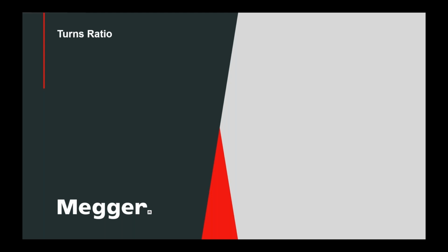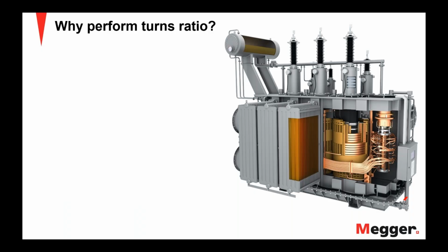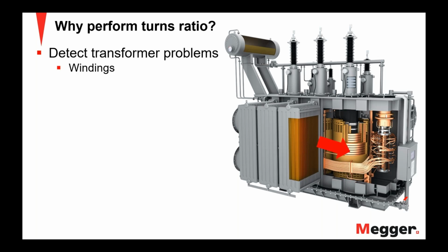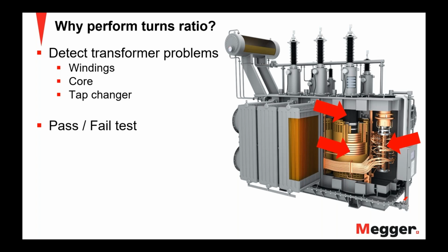But now if we look at the turns ratio test, what this product is built to do, why are we testing turns ratio? And I'm showing a large transformer here, not quite exactly the same as a small distribution transformer, but there are some common elements inside, mainly being the windings, the core, and the tap changers. If you use a voltage regulator, it does have a tap changer inside. And with turns ratio, you can look for problems like shorted turns or the core moving around, or problems with those tap changer connections as it's going through the different positions.